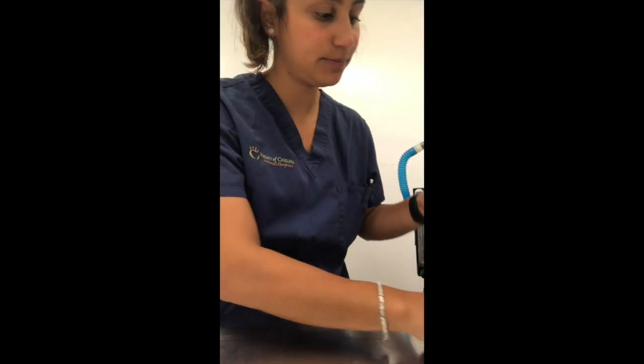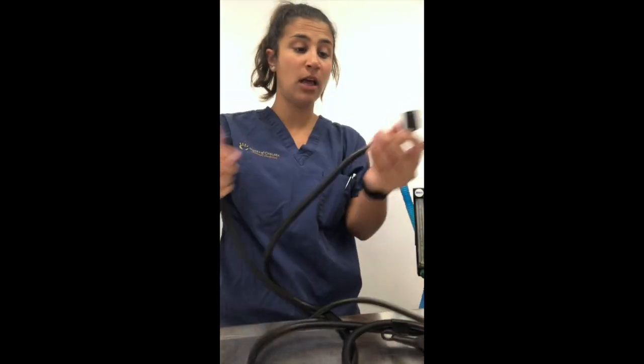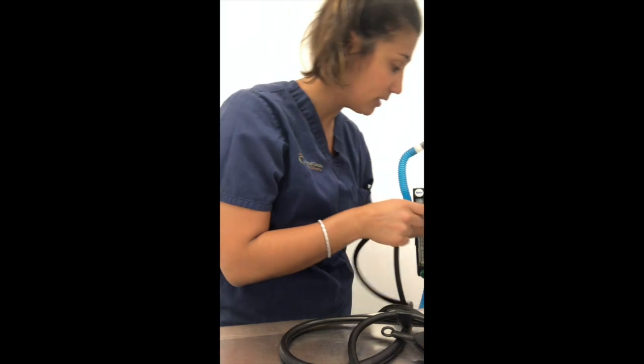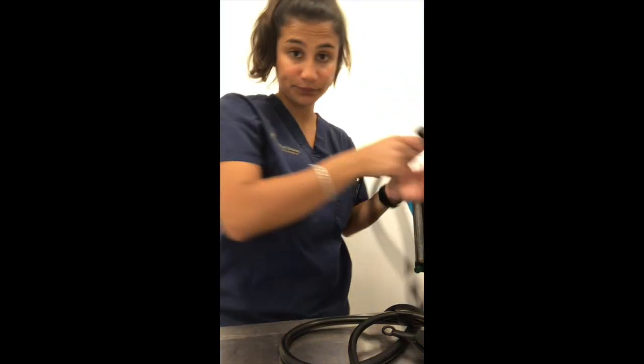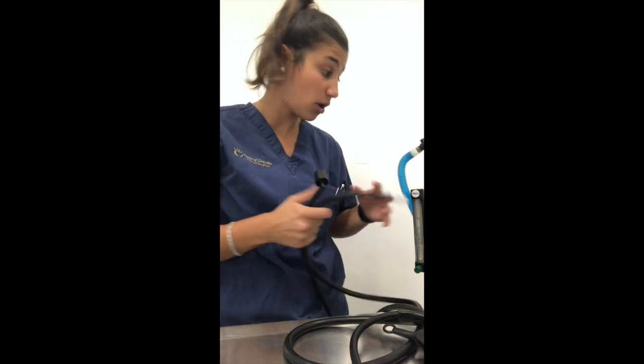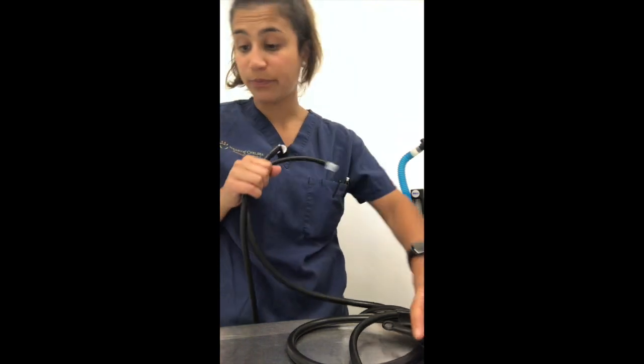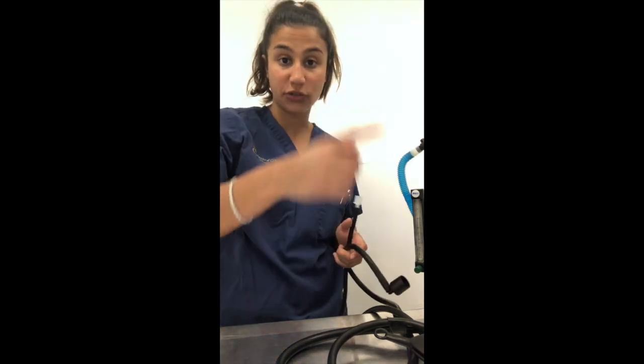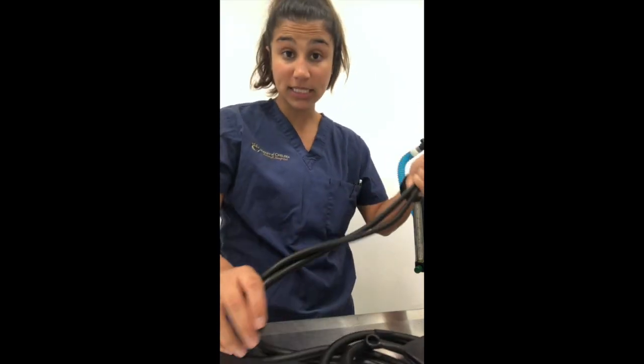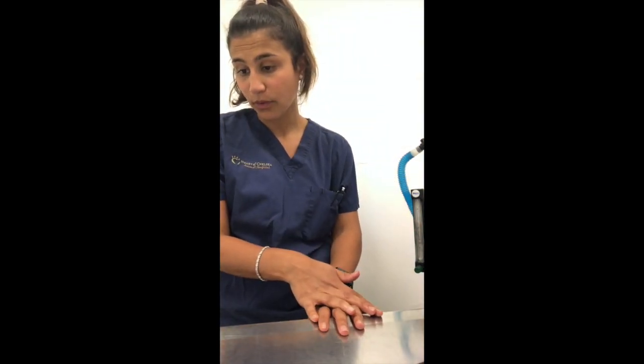In a non-rebreathing system, we would use a non-rebreather bag, like this one. In this one, this port is directed onto the outlet port right here, and then this goes directly into our anasorb. So this completely bypasses our carbon dioxide absorbent. The main reason for this is that the fresh gas is routed directly to the patient instead of recirculating into the system. The main difference between these two systems is that we would only use a non-rebreather for patients that are under 3 kilograms.